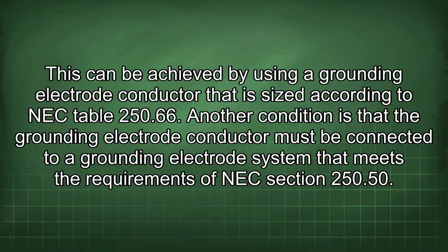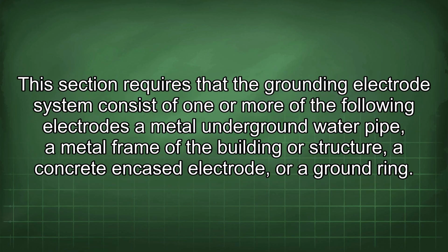This can be achieved by using a grounding electrode conductor that is sized according to NEC Table 250.66. Another condition is that the grounding electrode conductor must be connected to a grounding electrode system that meets the requirements of NEC Section 250.50. This section requires that the grounding electrode system consist of one or more of the following electrodes: a metal underground water pipe, a metal frame of the building or structure, a concrete encased electrode, or a ground ring.